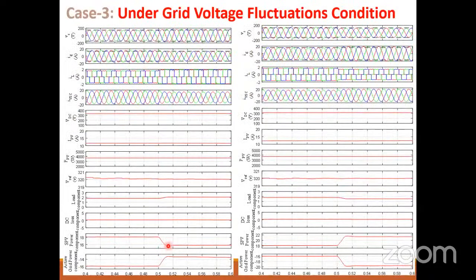Okay. Similarly, the same thing was tested under grid voltage fluctuation conditions, so you will see the over voltage conditions and under voltage conditions, when the voltage is fluctuating. So what is going to happen? If there is an over voltage condition, the voltage will increase on the grid, or under under voltage conditions, the voltage will decrease, then what will happen? Then the current will also change accordingly, right? Over voltage conditions, if the voltage increases, then the grid current will decrease. If under voltage, the grid voltage will decrease and the current will increase, because the power feeding into the grid is constant.